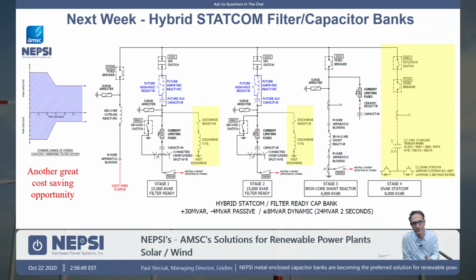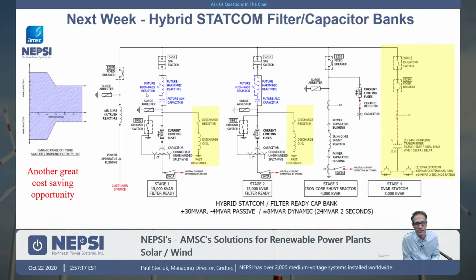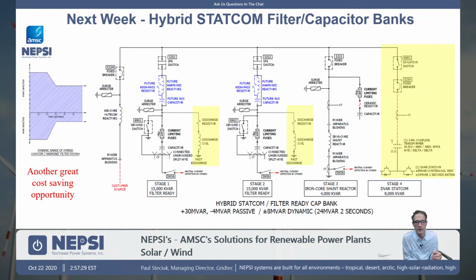And with us next week will be AMSC and their product engineers to talk about the hybrid STATCOM filter/cap bank systems. This is really a way to get additional cost savings by utilizing an integrated solution that includes a STATCOM system and also the capacitor bank itself. We can install fast discharge within our cap banks, and basically we can get an improved dynamic performance, and we're going to be talking about that next week. How we can improve the dynamic performance of a STATCOM, increases its ratings because we're using a hybrid solution which consists of capacitor banks with fast discharge and STATCOMs, all built in to one piece of equipment.